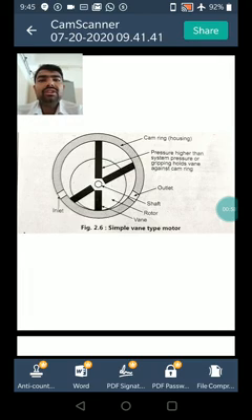The high pressure on the inlet side and low pressure on the discharge side of a motor generates side thrust. To eliminate side thrust, the inner contour of the cam ring is made elliptical instead of circular. This establishes a pressure balance in the vane motor and develops a torque of up to 1600 Newton millimeters with a speed of about 100 rpm.